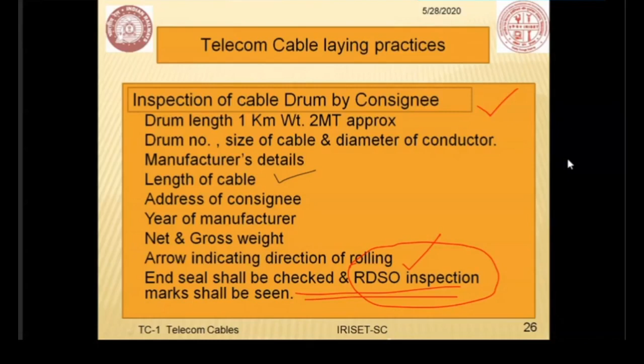First, visual inspection. There is every chance of damaging the cable drums and cable during loading, unloading, and transportation. In such cases, you cannot blindly accept the cable just because RDSO's inspection certificate is there. That is not how it works. You have the right to point out issues, and by making proper remarks, you can reject the cable even if it is certified by RDSO, if sufficient ground is there and suitable remarks are made.